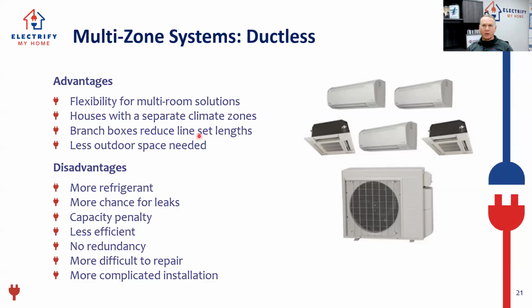Branch boxes reduce line set lengths, but not always. We installed a system like 4 years ago. There was no other way to do this house than with a ducted system for the upstairs bedrooms, a ducted system for the downstairs, and a wall mount for the basement room. There was no way to do that other than that. And we used one of these with a branch box. But the unit had to go out back because the city was persona non grata on putting a unit on the side of the house. So they're like, it's got to go in the back.